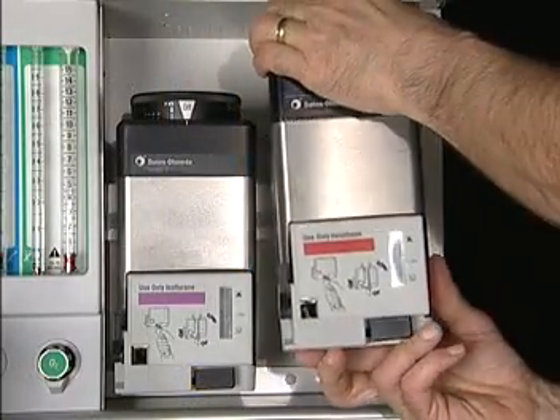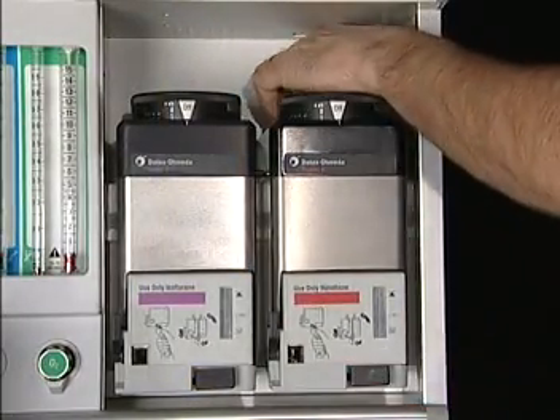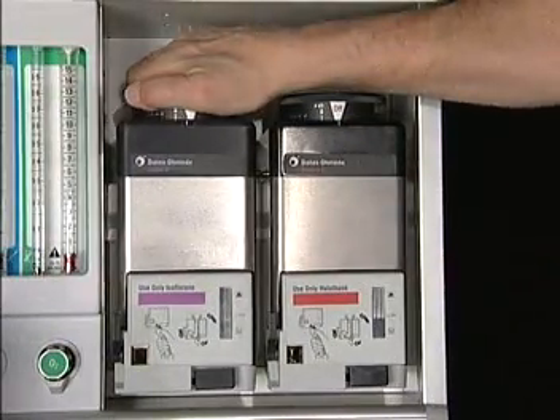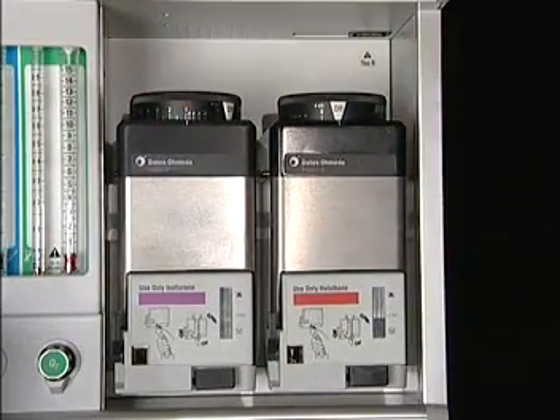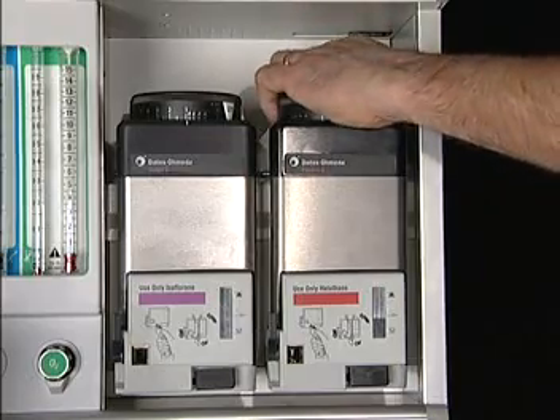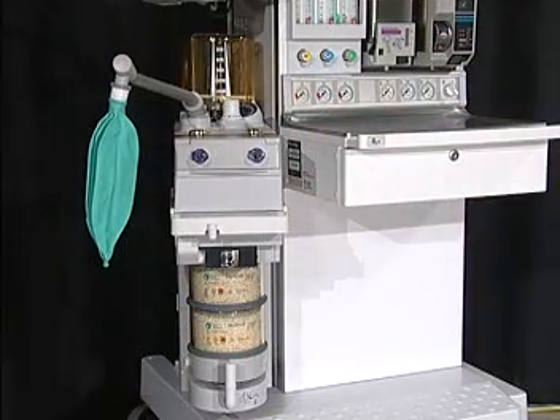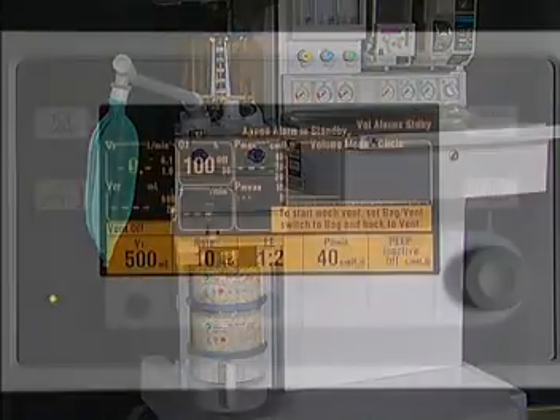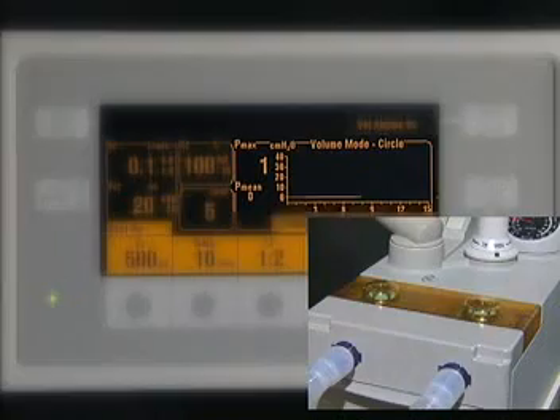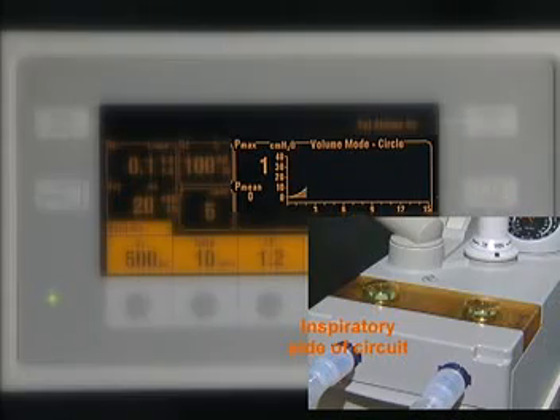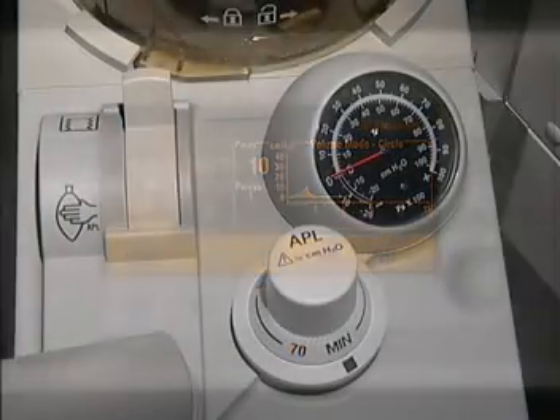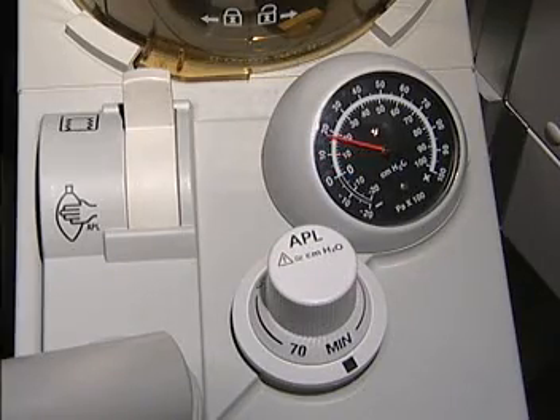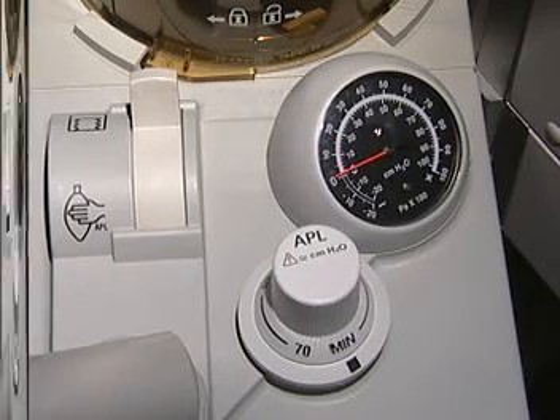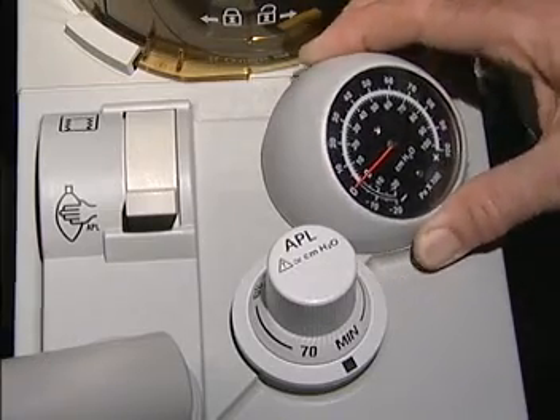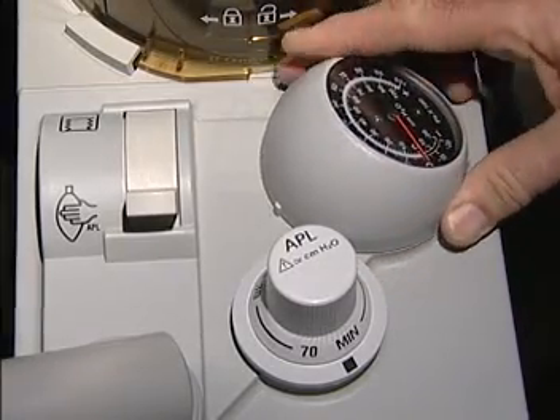Ensure the vaporizers are properly placed and locked on the Select-a-Tec manifold and have agent. The Select-a-Tec manifold will only allow one vaporizer to be operated at any time. Gas flows internally from the vaporizer to the breathing system. Breathing system pressures are sensed on the patient side of the inspiratory check valve and are displayed on the ventilator screen as well as on an analog gauge located on the breathing system. The gauge can be rotated for viewing at the desired angle.